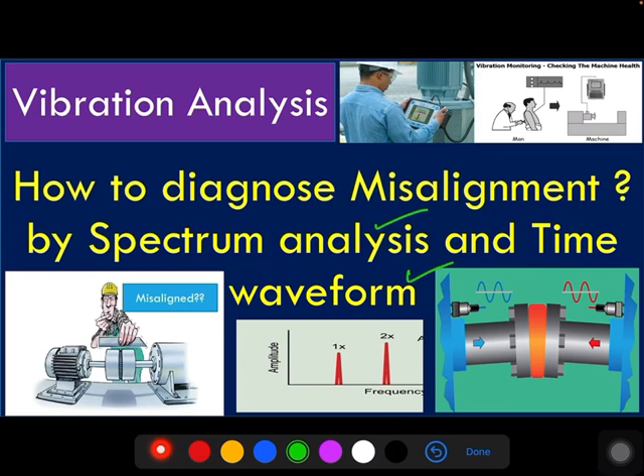In industry, the majority of machine failures are due to misalignment. This misalignment adds additional load in the form of stresses and also puts additional forces on the bearings. Misalignment damages the seals, bearings, and couplings, and also causes the shaft to bend. So vibration analysis is an important tool to diagnose the misalignment condition in any equipment.